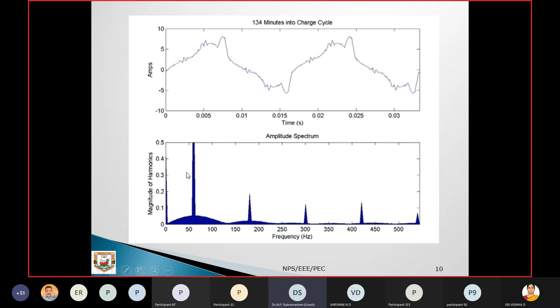When THD values are much higher, it produces unwanted current, neutral current, as well as unwanted heat and unwanted noise. It produces a lot of effect and stress on the system. This must be taken care of, otherwise the system gets collapsed. That's a big challenge in this topic.